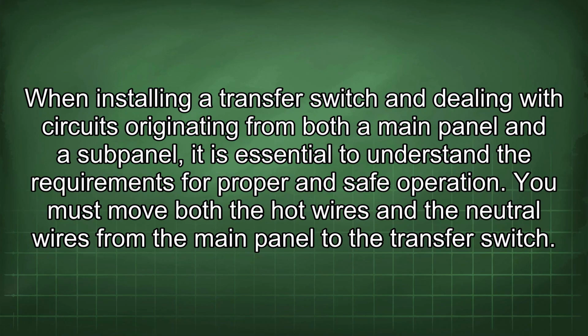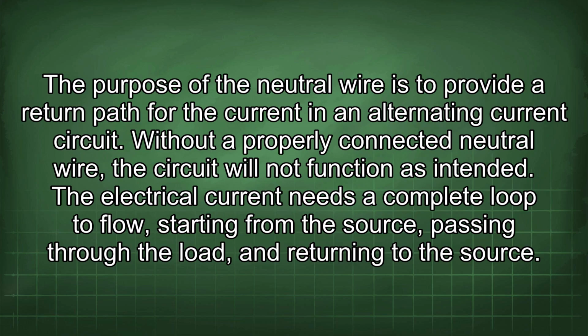When installing a transfer switch and dealing with circuits originating from both a main panel and a subpanel, it is essential to understand the requirements for proper and safe operation. You must move both the hot wires and the neutral wires from the main panel to the transfer switch. The purpose of the neutral wire is to provide a return path for the current in an alternating current circuit. Without a properly connected neutral wire, the circuit will not function as intended.